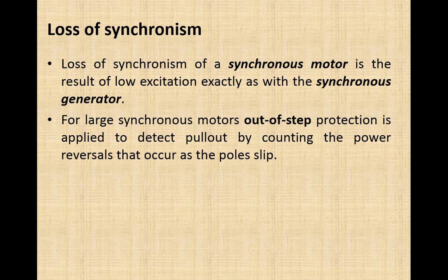As soon as this pole slip occurs, there will be a pulse of reverse power towards the system from this motor, because the motor will act as a generator for that short duration, which could be a fraction of a second, but that pulse could be counted in order to detect that pole slipping has occurred. So this out-of-step protection is actually counting that power reversal.